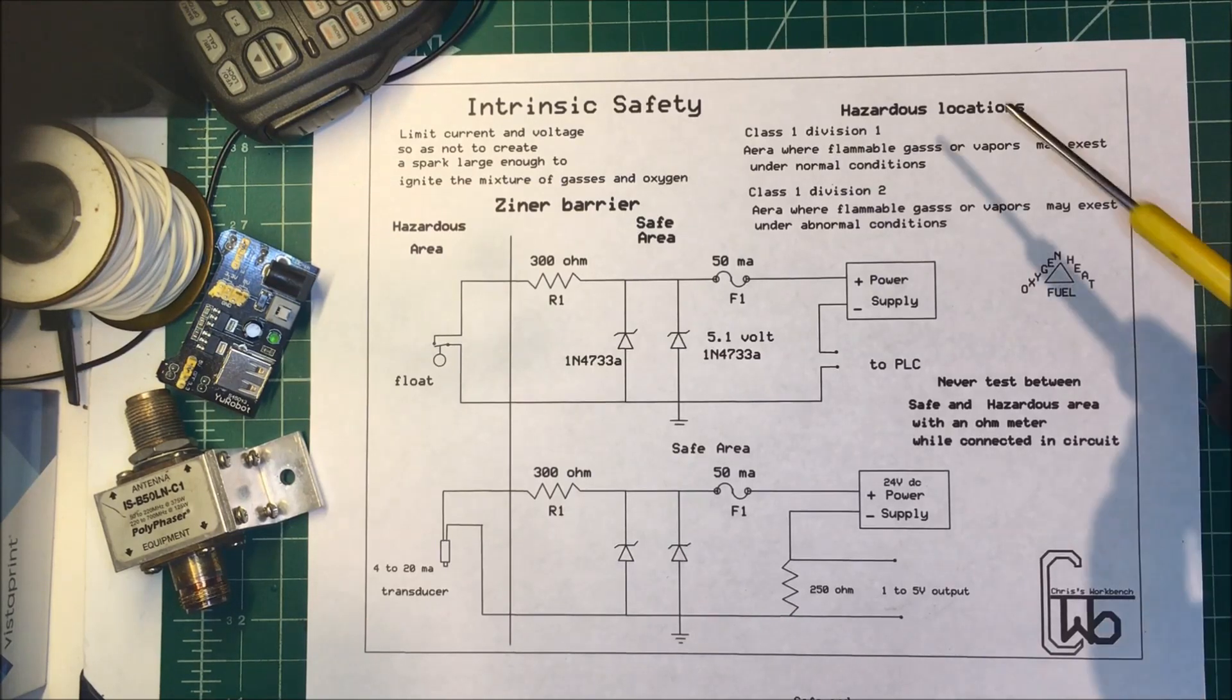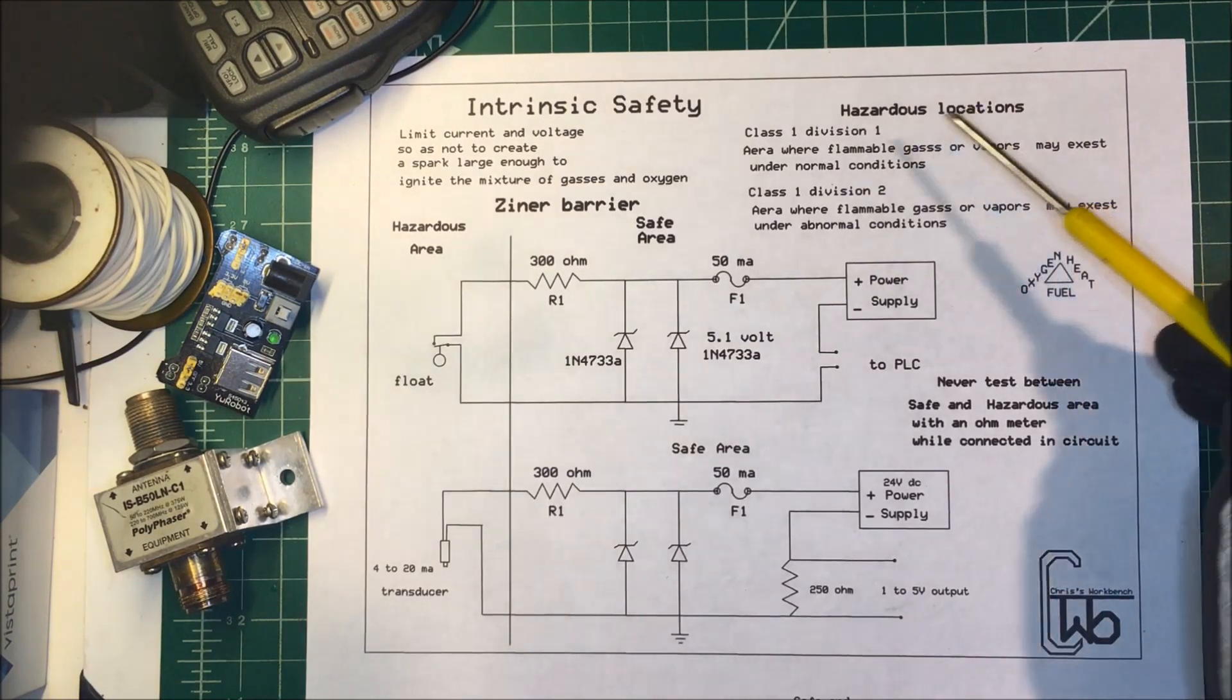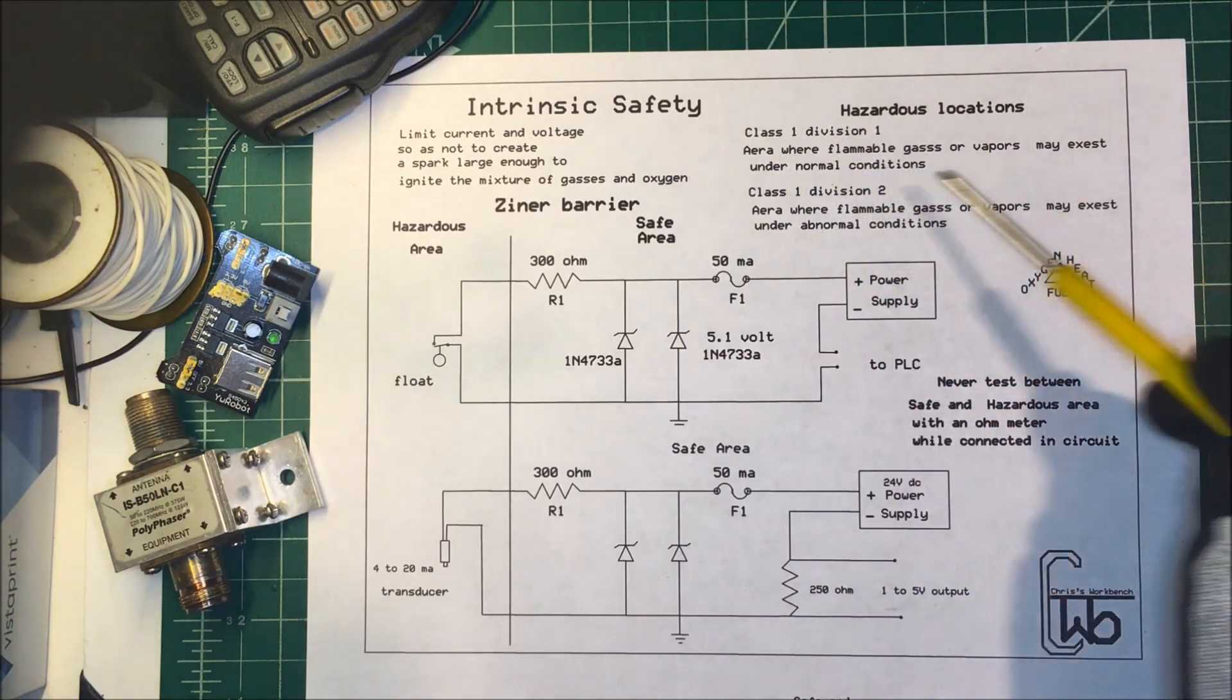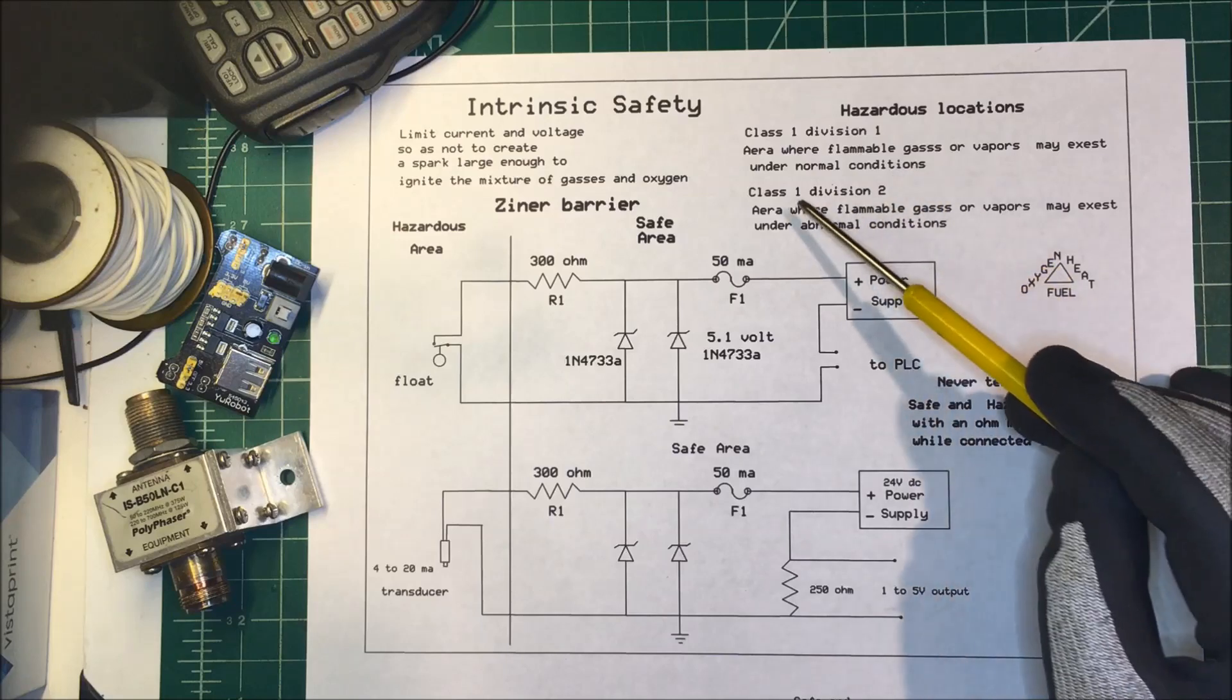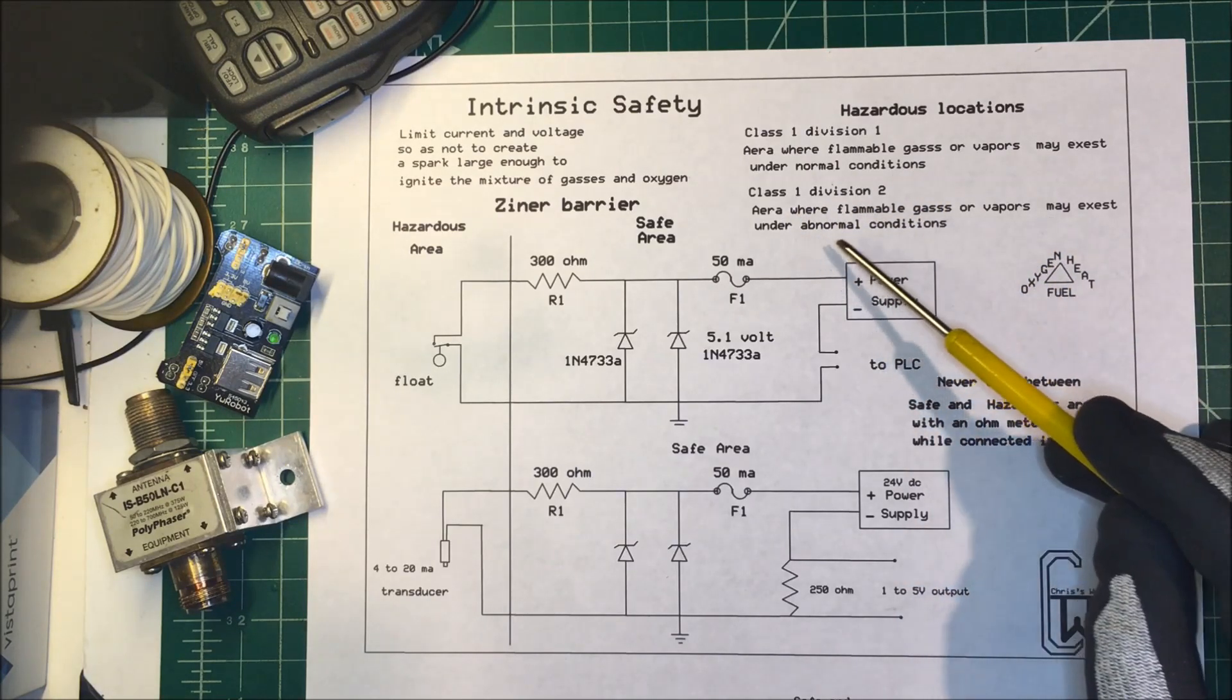Let's talk about intrinsic safety. The National Electric Code classifies hazardous locations. Class 1 Division 1 is an area where gases and vapors may exist under normal conditions, and Class 1 Division 2 is an area where flammable gases or vapors may exist under abnormal conditions.